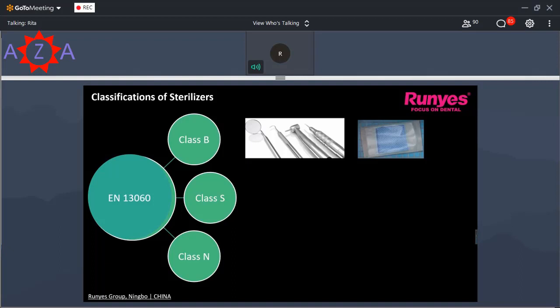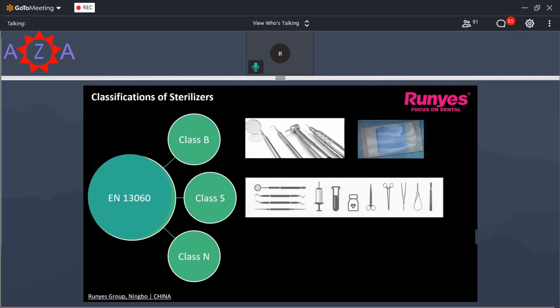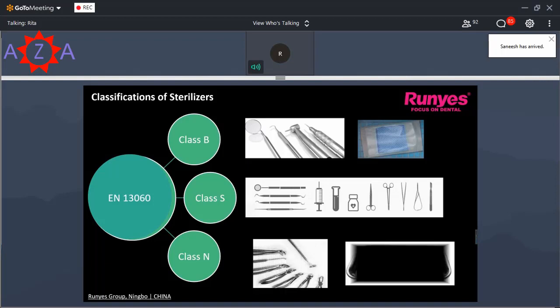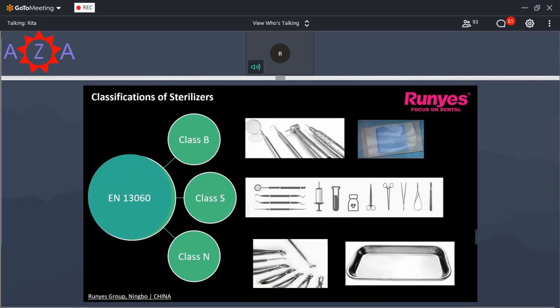And for wrapped solid products, and items like small hollow instruments and lumen devices without packages, we require an autoclave with at least 1 pre-vacuum to do the sterilization. So this is Class S. The Class N autoclave is intended to sterilize non-wrapped solid items. So I hope this makes the classifications of sterilizers easier to understand. Most countries have regulations to use Class B autoclaves only, including China. China also requires only Class B autoclaves.